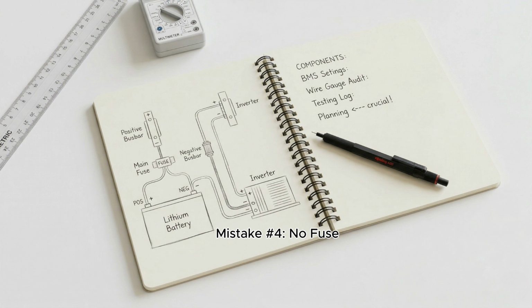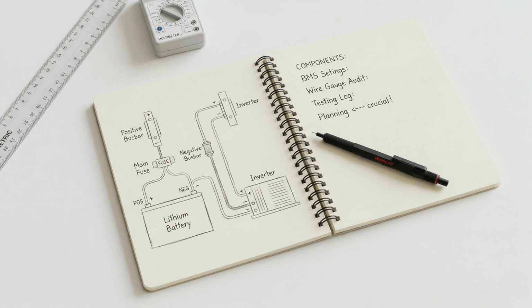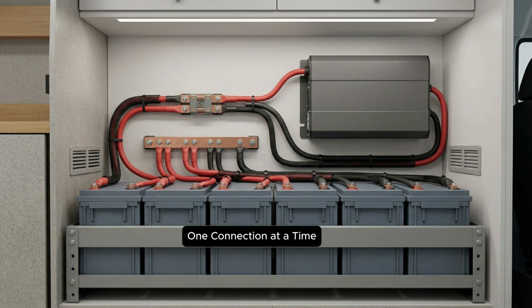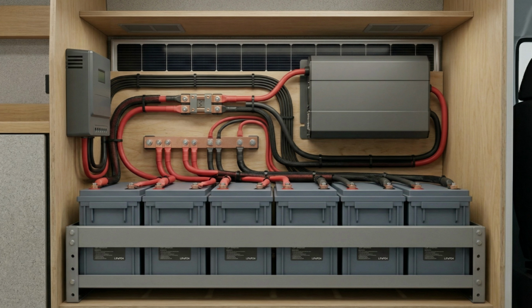The fourth mistake is skipping fuses or circuit protection. This is one of the most dangerous mistakes in the entire system. Fuses and breakers are not optional accessories. They are your first line of defense. If a short circuit happens, the fuse is designed to interrupt the current before the wire overheats or turns into a heating element. Without proper protection, a lithium battery can release extremely high current in seconds. That is what makes this so serious. You are not dealing with a weak power source. You are dealing with a very capable battery bank that can dump energy fast.